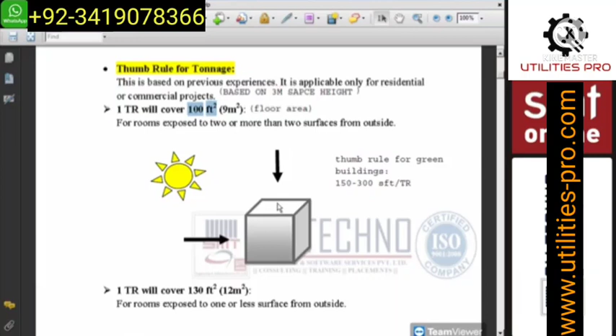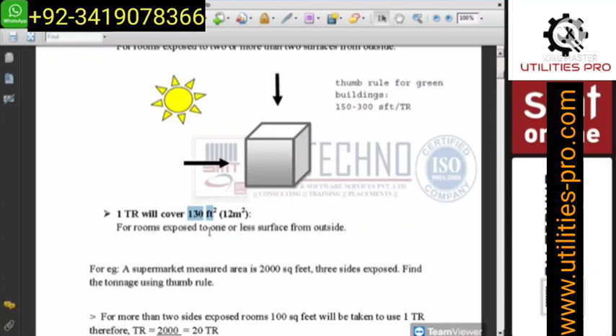Suppose the roof is exposed, and another side is also exposed. But we have multiple rooms inside the building which are not exposed. Only the corner rooms or the perimeter rooms are exposed, or on the top floor we have the roof, but other rooms are not exposed. So in that case, 1 ton will cover up to 130 square feet of area, for rooms with 1 exposure or no exposure. Okay, so this is the thumb rule, and it is for a standard project.